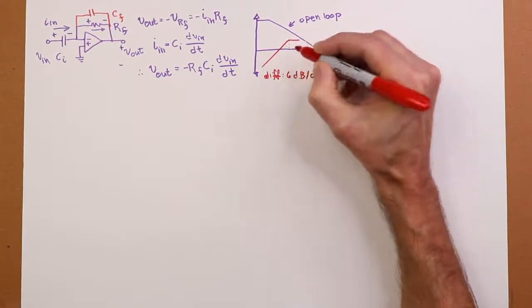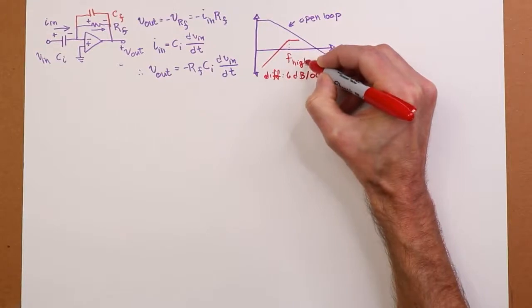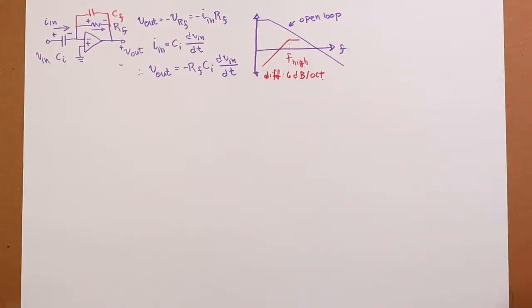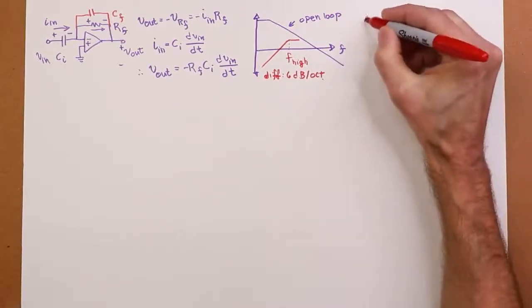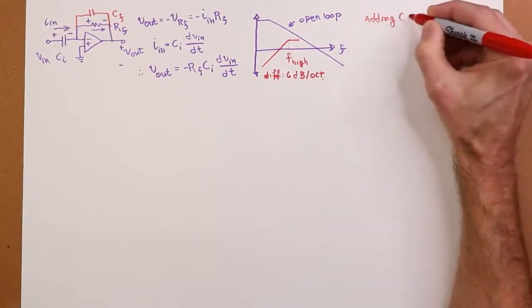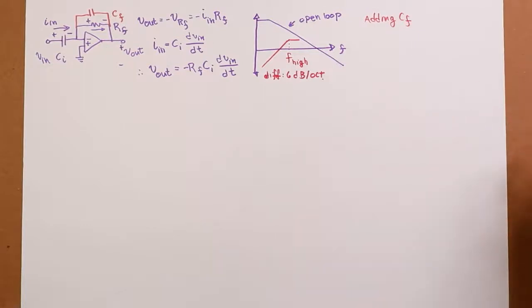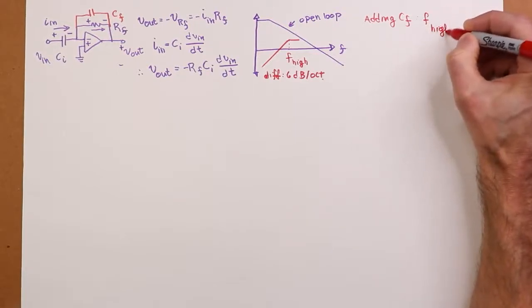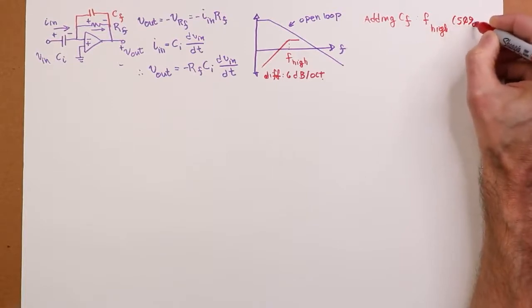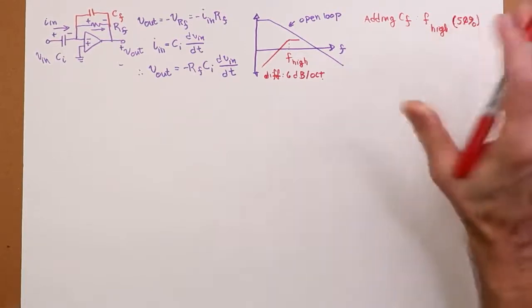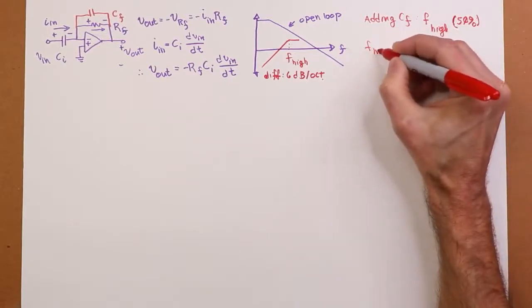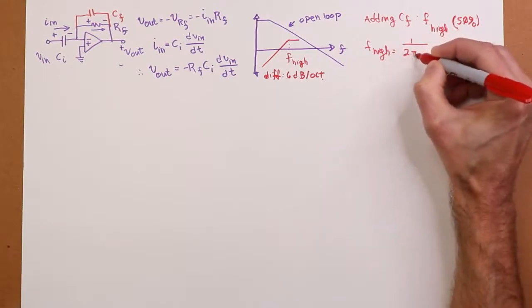So this is going to flatten out, and right here is F_high. That's the upper limit of differentiation. Differentiation occurs on the 6 dB per octave slope. So adding C_F limits the noise, makes the system more stable. It creates an F_high, which we can call our 50% accuracy point. F_high is equal to 1 over 2π R_F C_F. Just where is that critical?